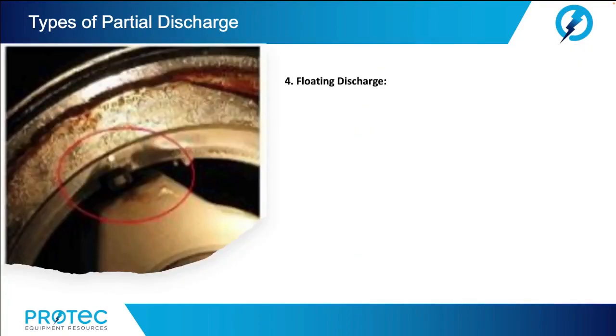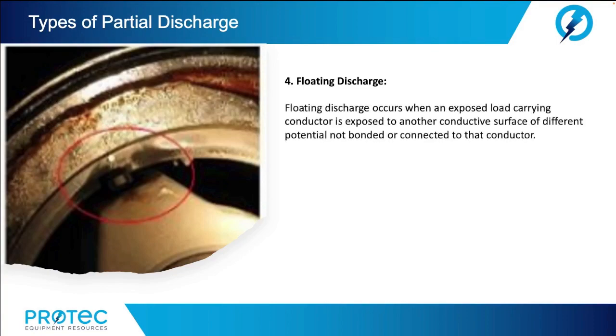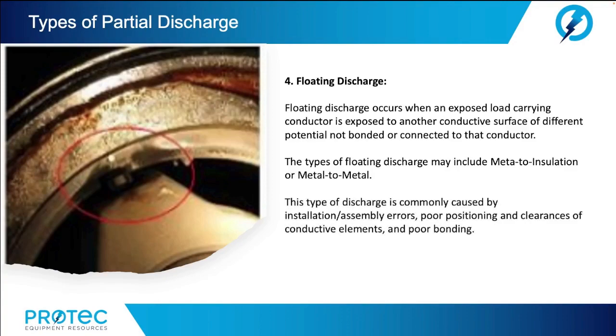Number 4, the floating discharge. Floating discharge occurs when an exposed load-carrying conductor is exposed to another conductive surface of different potential, not bonded or connected to that conductor. The types of floating discharge may include metal to insulation or metal to metal. This type of discharge is commonly caused by installation assembly errors, poor positioning and clearances of conductive elements, and poor bonding. Floating discharge is a very common type of PD.